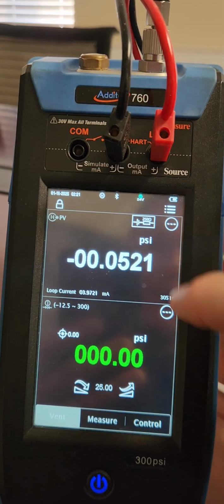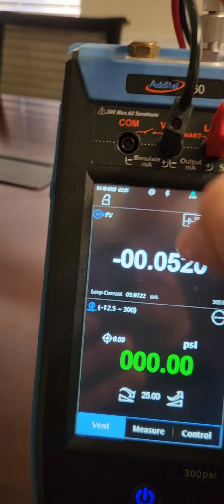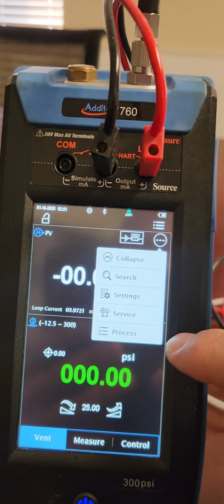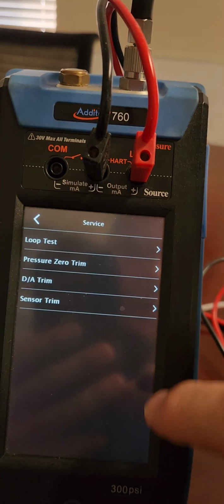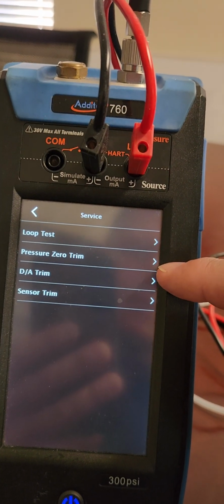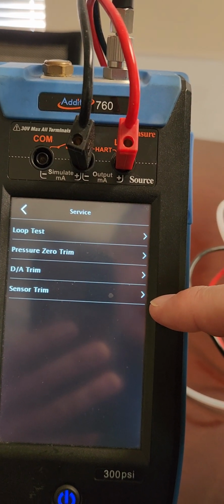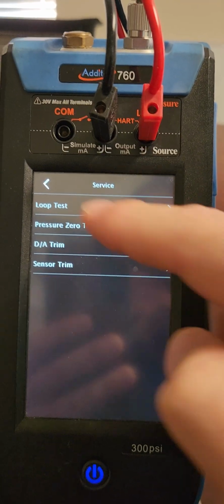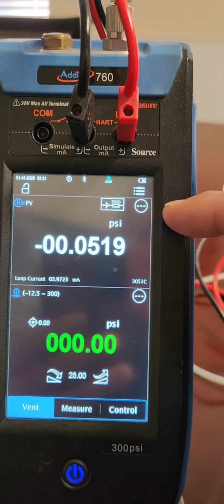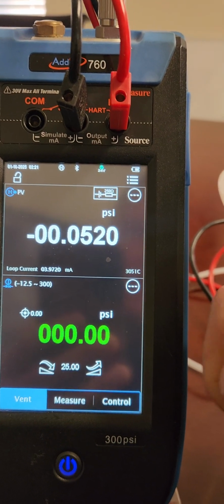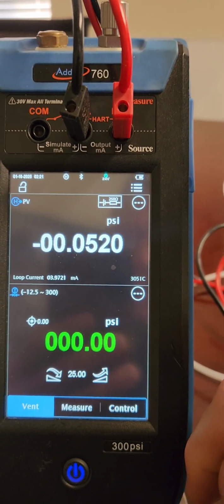So if we need to make adjustments to this, then I can go back here to the beginning, unlock that, and then I go to services, and then here I can do like a loop test, a 0 trim, a sensor trim. So whatever you need to do to adjust this is all found here in this main screen. Once you do an adjustment, you can go back in and take as left data, and then your calibration will be complete.